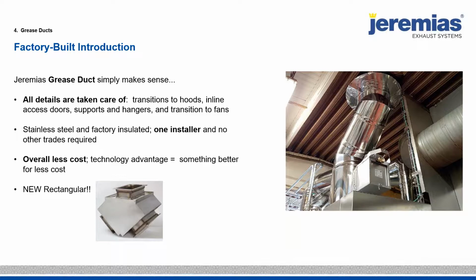this is for the first time probably since the history of factory built, the factory built systems are actually less cost than welded steel, than insulating it twice in the field. So the great thing about this is that you have one installer and you don't have to have multiple trades when you do a kitchen ventilation system.